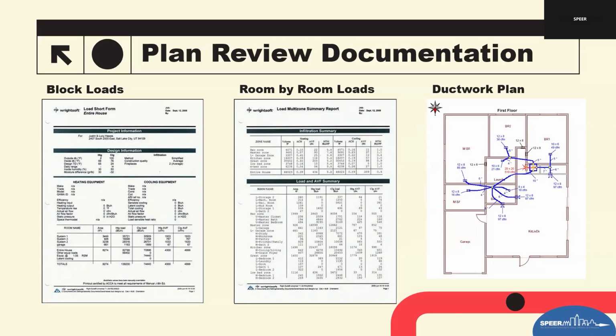It just shows the supply boots, where they're going to be installed in the room, the number of returns, where the return is located, and then the CFM that's actually being produced, or should be produced, into those rooms. It's also showing the size of the boot or register that will be in there, and the duct size as well. The one thing I do see missing is duct length. But on that part of it, we really need a room-by-room load in the Manual J, not necessarily just a block load.